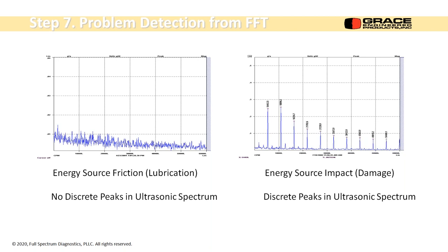So you can do a spectrum of that sawtooth waveform. And if there's no sawtooth peak in there, there's just noise floor, random noise, you'll see something like that. So every survey, this will go up and down a little bit. We can trend the overall level of that energy. If it is a discrete peak due to a piece of raceway coming out, little chunk of metal being separated, you'll see a discrete peak show up, a discrete impact, and a whole string of harmonics. So you should be able to identify the source. This should be non-synchronous, and it should equate to an inner race or outer race defect frequency.